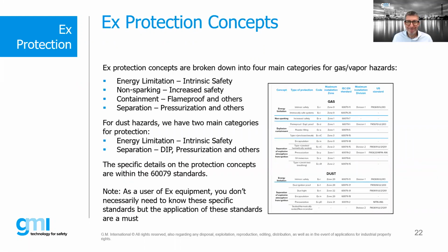Let's move forward. So the protection concepts, and we'll really focus our attention again on gas environments. So there are basically four main categories for gas vapor hazards and how we deal with them. So energy limitation on the left-hand side, that's really, again, intrinsic safety. This is where we're limiting the amount of energy. We also have what is called non-sparking. So increased safety, which is considered to be EXE. We also have containment, and there are a couple of different protection concepts such as flame-proof, powder-filled. So we're containing an explosion inside of some sort of housing, if you will. And then finally, separation. Separation is basically removing, in effect, either the gas or vapor from any potential ignition source. A common one that we use is pressurization, or EXP.